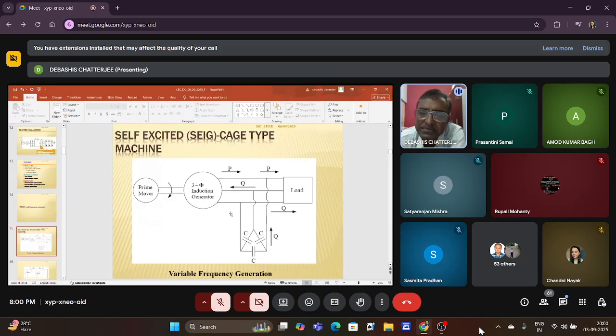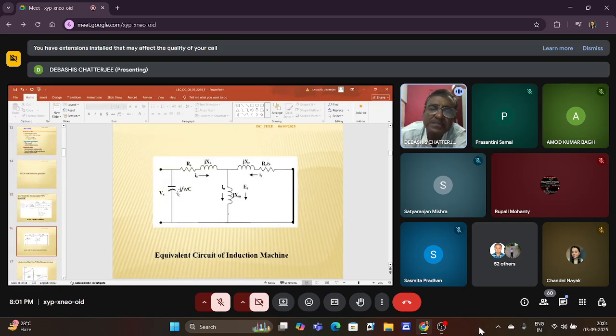Now it is not shown connected to the grid. Why? Because, as you know, here it is a variable frequency generation, variable speed system. The overall voltage generated at these terminals is of variable frequency, variable voltage nature, just like the synchronous generator or alternator at variable speed we have seen, right? Now, you see here, this is the equivalent circuit. The method of excitation is like this.